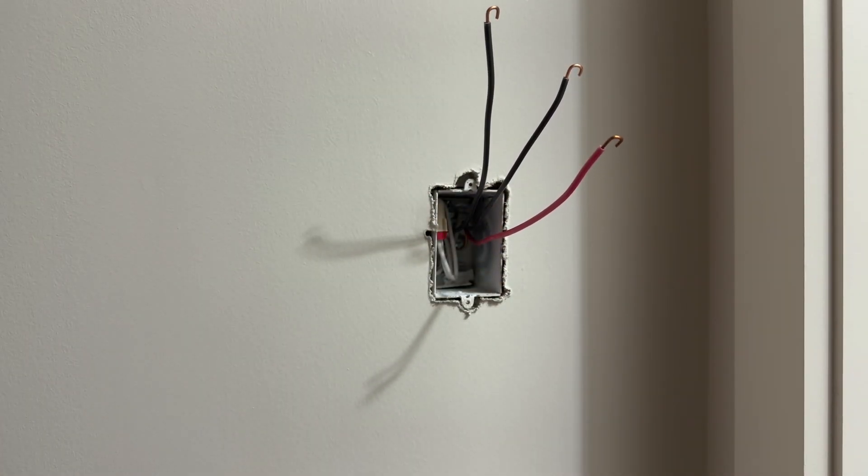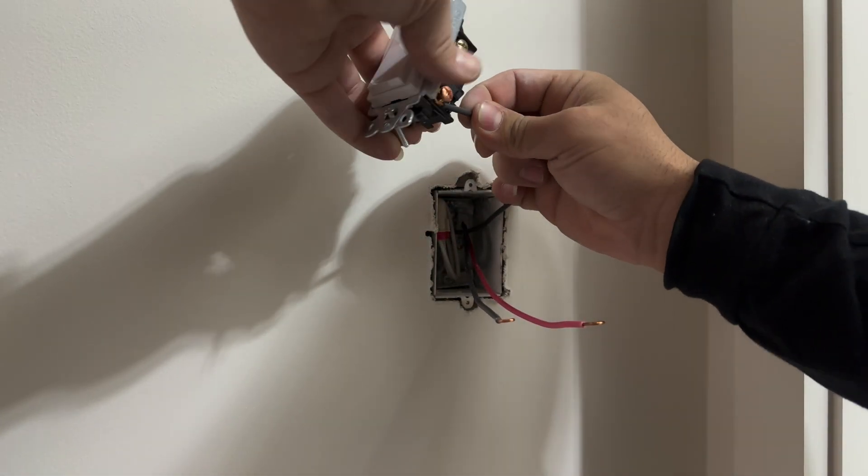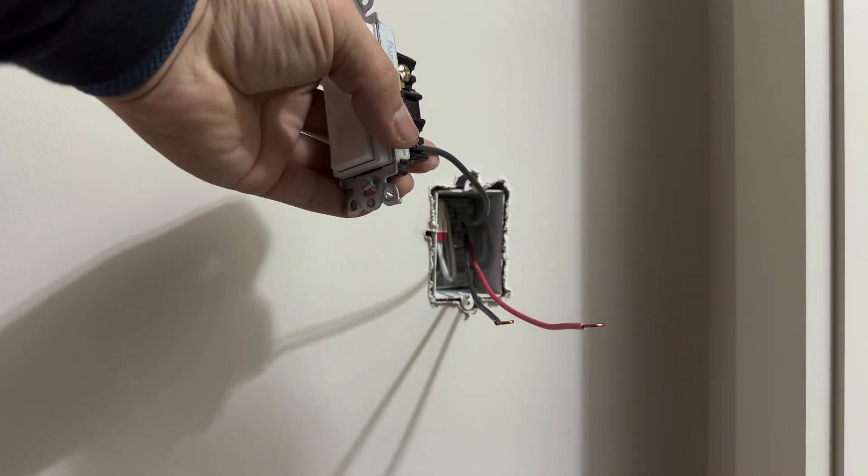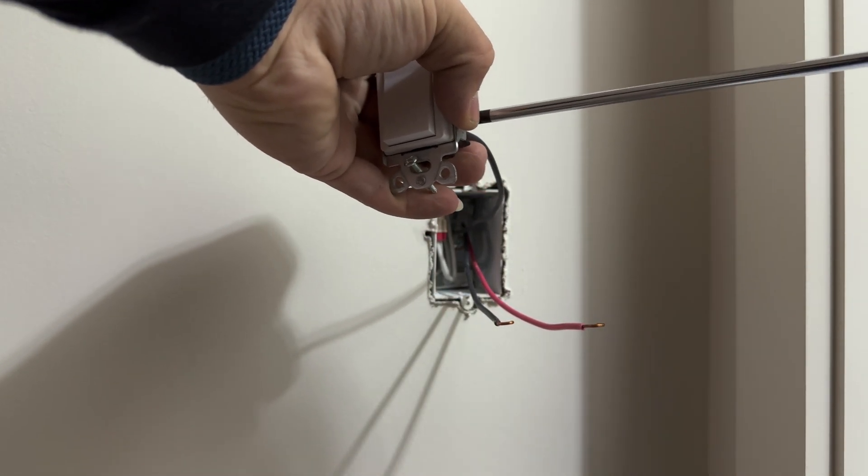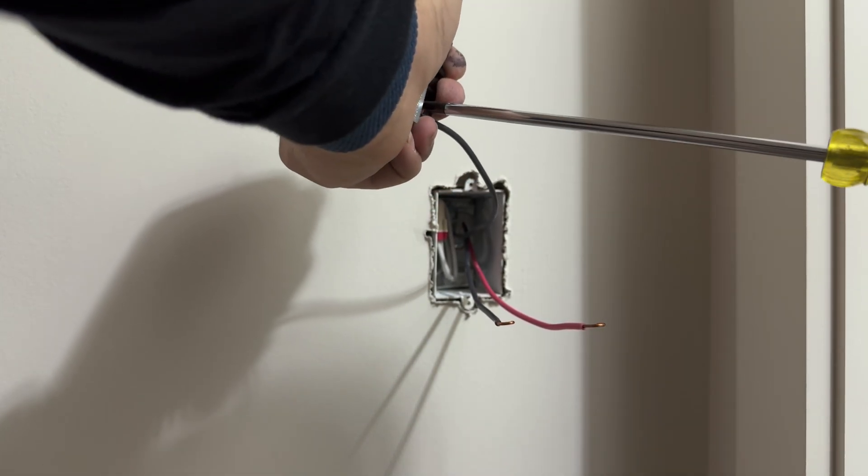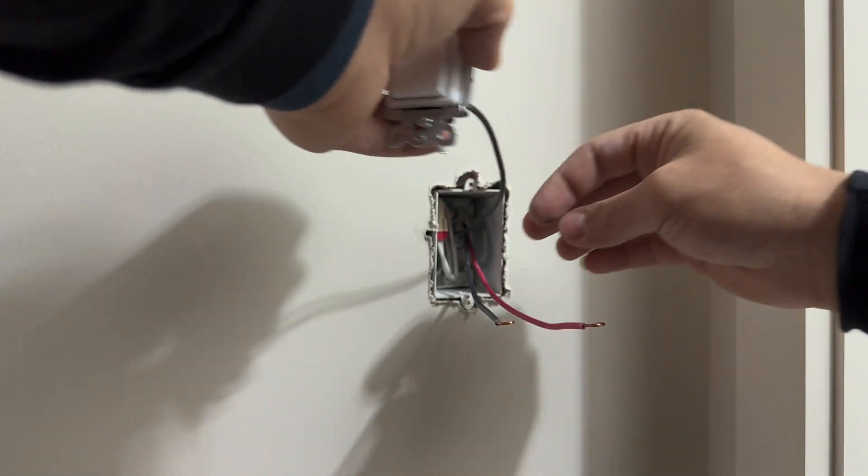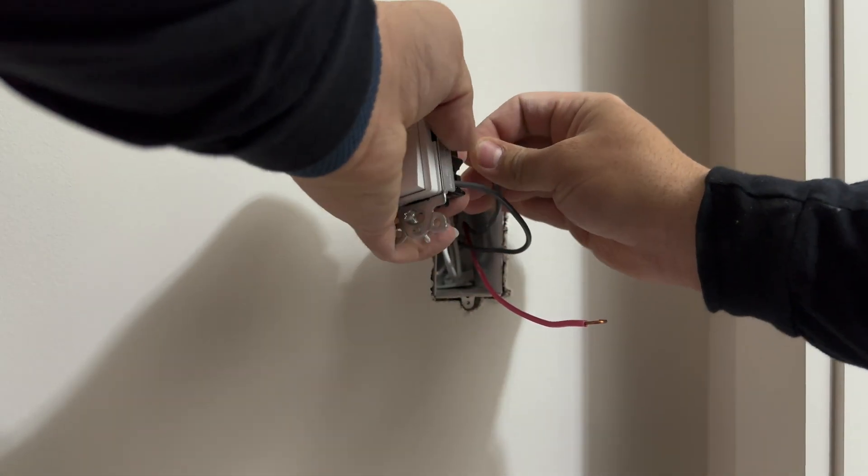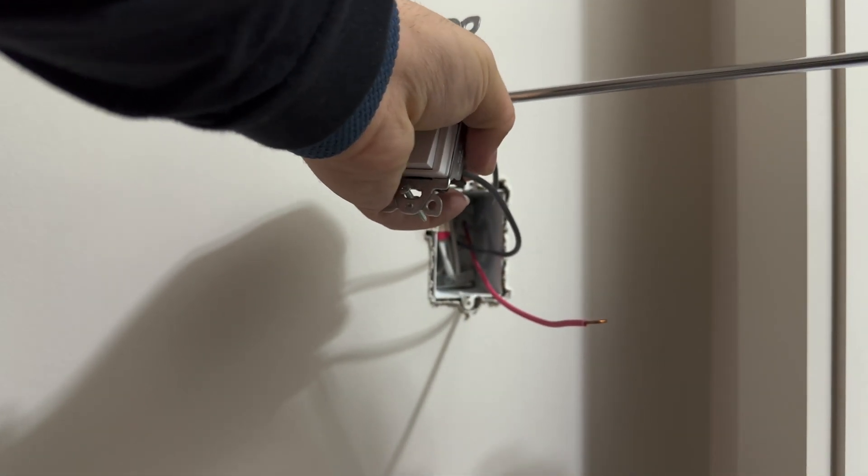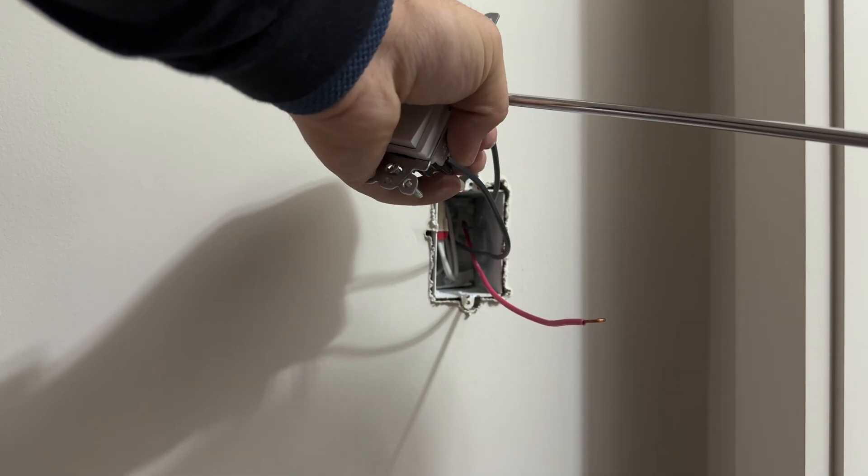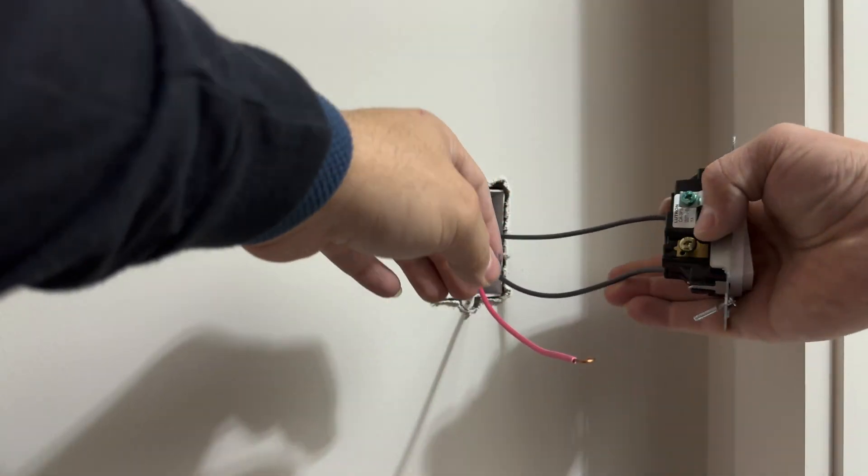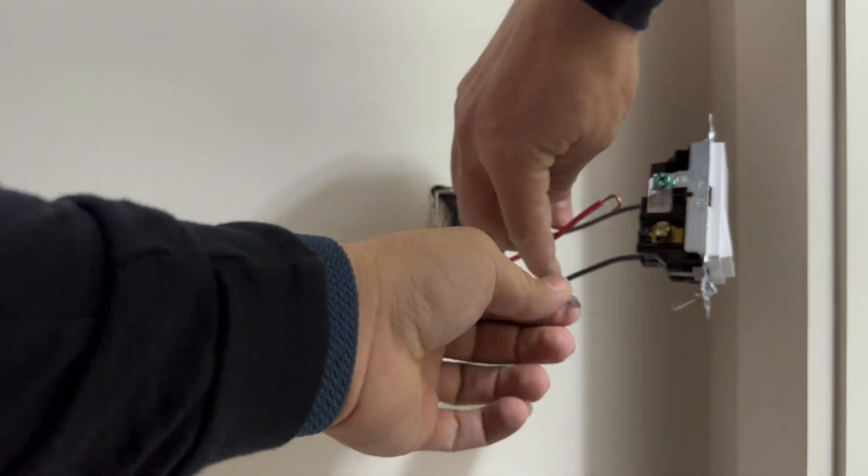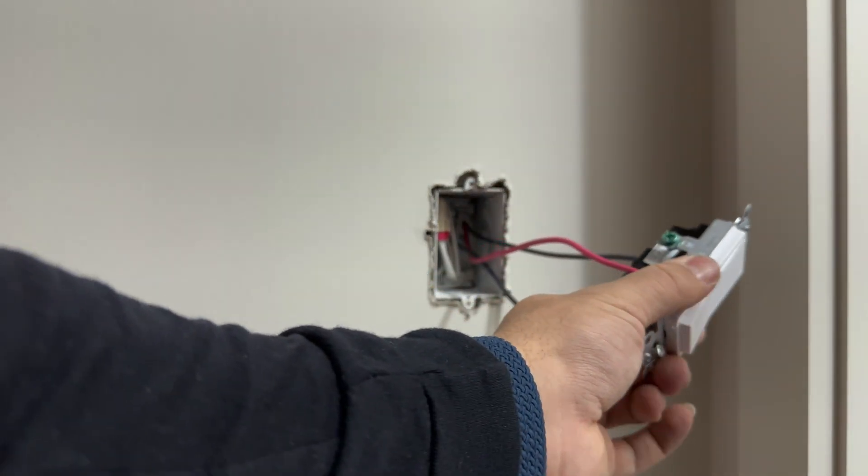All our loops are made, so like I said the switch leg will go in the screw for the common. And the power wire from the three-way conductor will go on the top screw and the red wire will go on this left screw as a traveler.